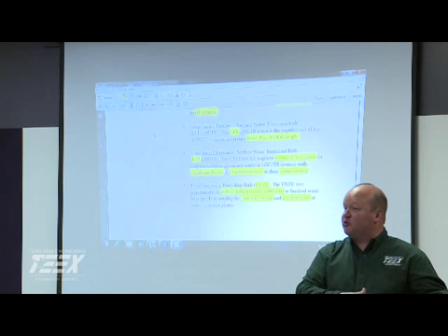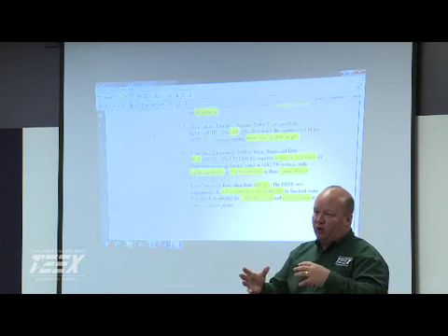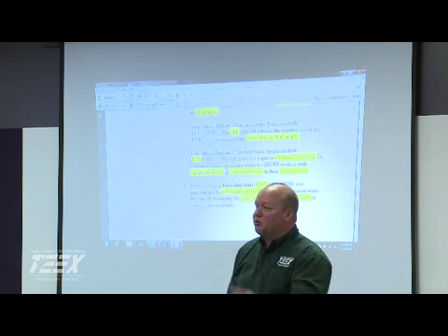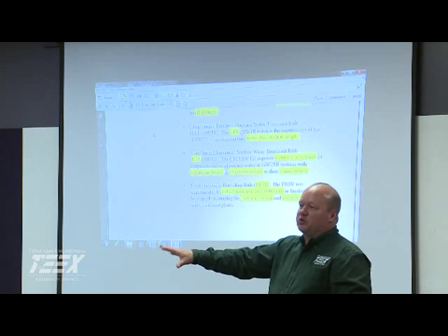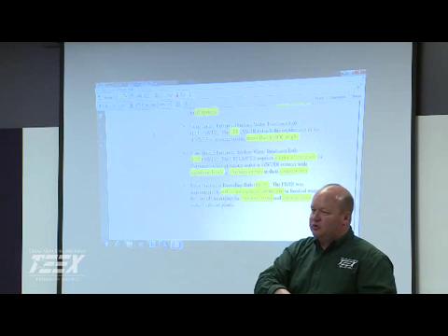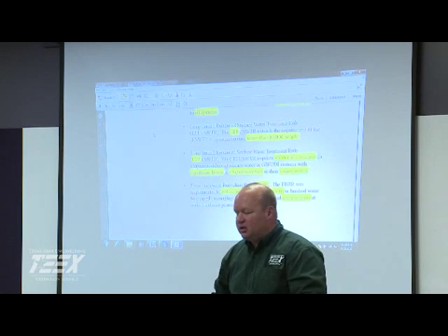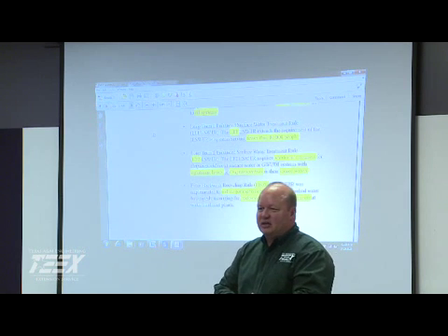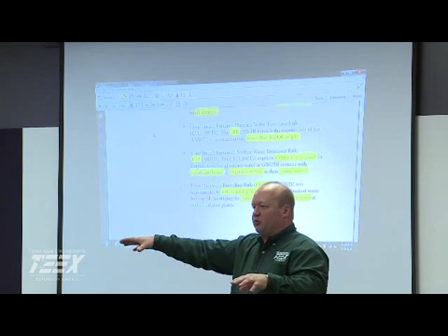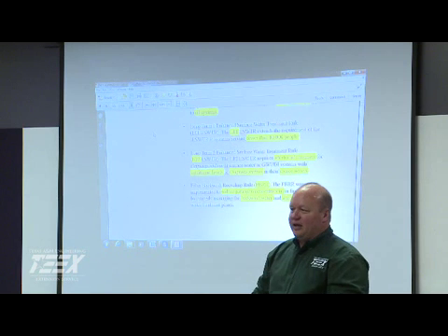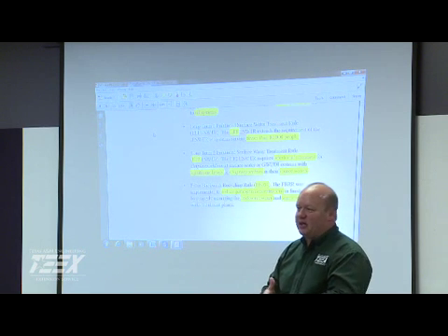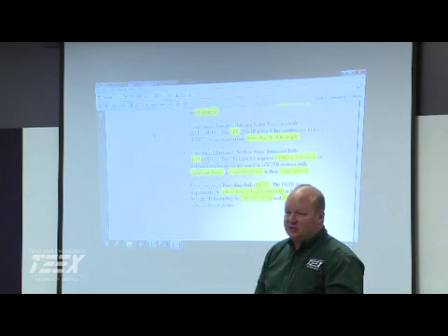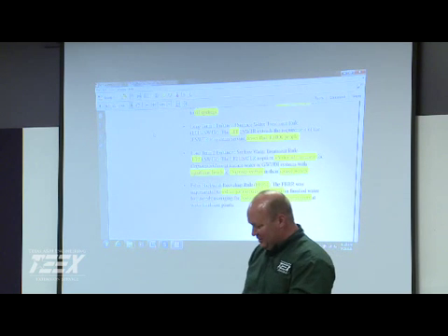So when we started doing some of the surface water components, you start to realize all the dance you have to do with the water chemistries. And of course, we were doing just the opposite. We had to take water that most people thought was pretty good, and we had to harden it up. So we did just the opposite of a lime softening process. It was interesting trying to optimize it. And then the plant had several different modes. Sometimes you're in recharge mode, sometimes you're treating the water, and it sits for 6 months. Equipment doesn't like to sit. Trying to get back out there and figure out what you did last time. So it was a lot of interesting work, but I have a great appreciation for surface water treatment.